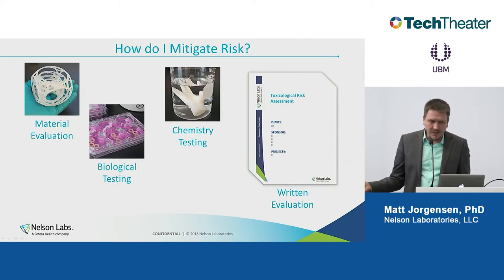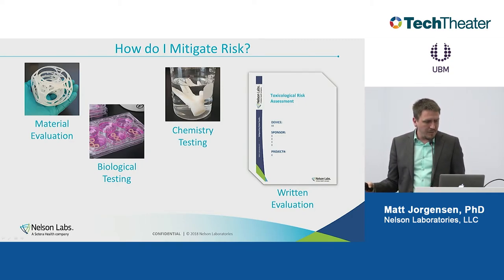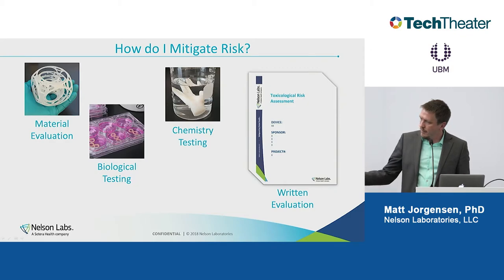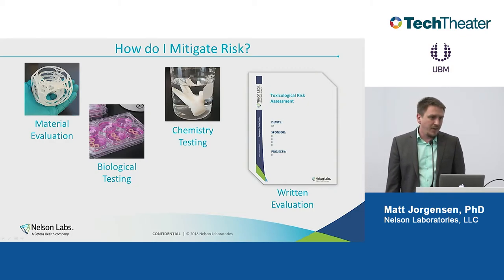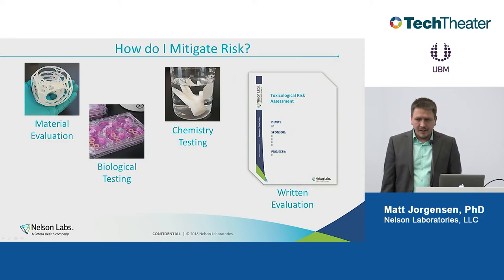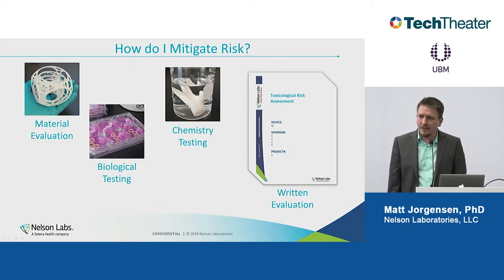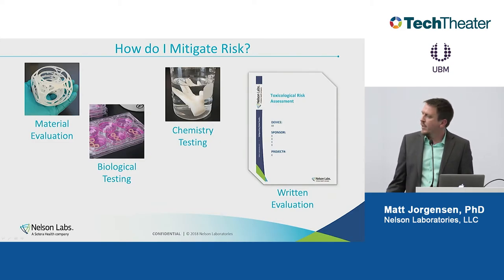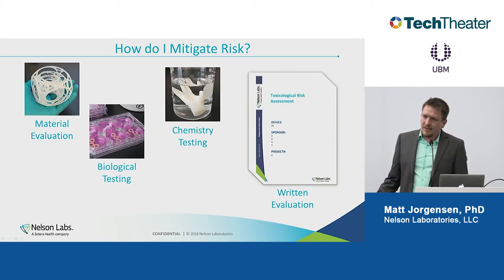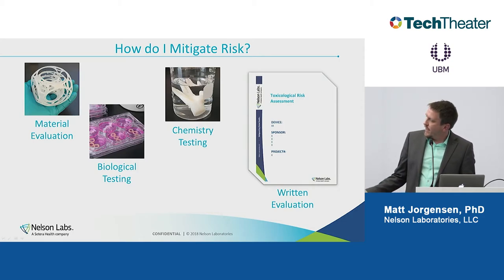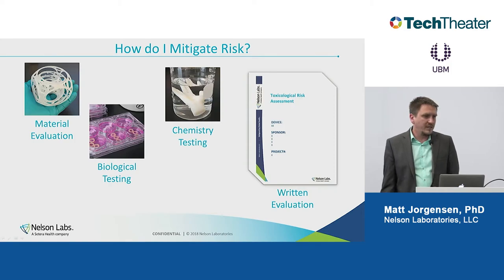So you have the option for material evaluation - this is coming more in the front end in the BEP. Of course, there's all the regular tests we're familiar with. Chemistry testing is a big thing now - if you have a permanently contacting device where you need to demonstrate biocompatibility, and you're not doing chemistry testing, then you're probably wasting around $200,000 and probably 6 weeks of your time. It's very well accepted by the FDA, routinely done now to address the longer term, more burdensome biological endpoints. And then written evaluations can also be a part of this strategy to address biocompatibility.